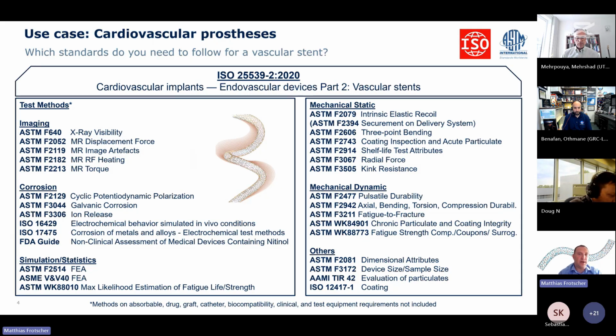ISO 25539-2 is part of a series of standards, with -1 for endovascular prostheses and delivery systems, -2 for vascular stents, -3 for vena cava filters, and -4 for coated endovascular devices. In case of cardiovascular implants, most of the other standards, especially material specs and test methods, are on the ASTM side, like coat hangers underneath the ISO umbrella document. The reason for this is the much faster revision cycles at ASTM, allowing for more up-to-date changes.